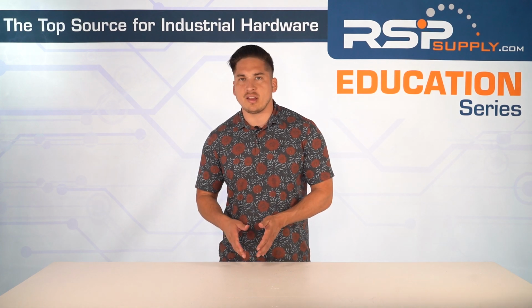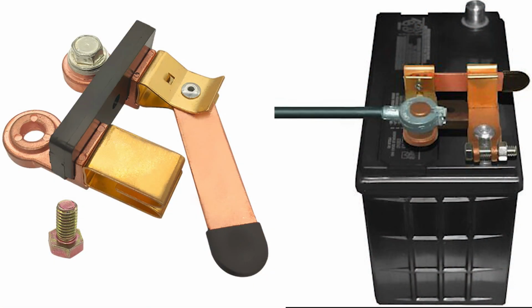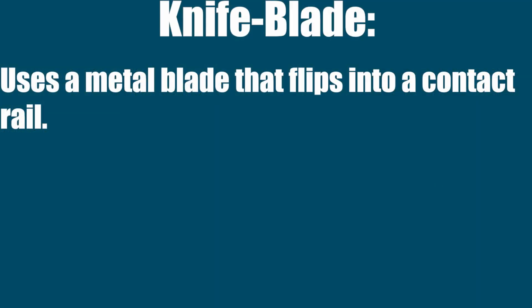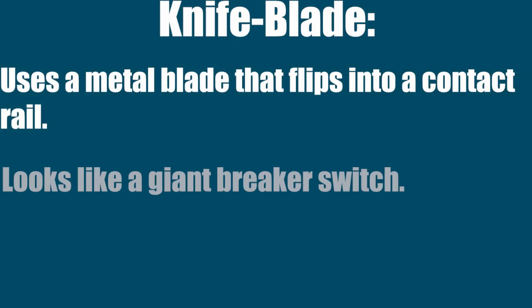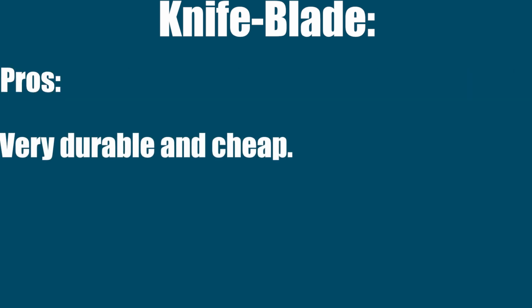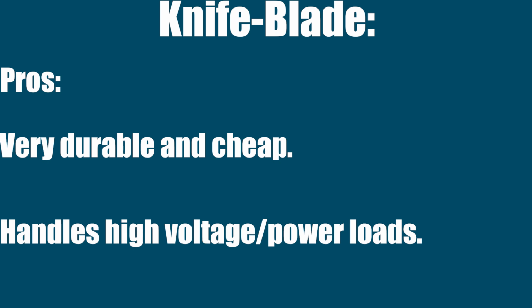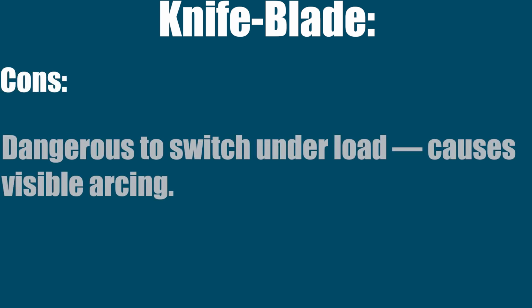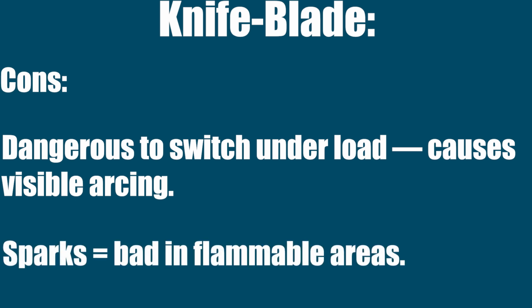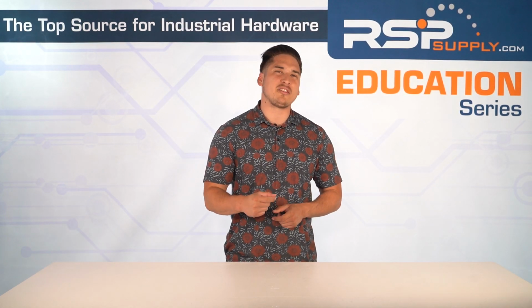Let's talk knife blade versus rotary versus molded case disconnects. So knife blade disconnects, this is old school tech, but still in play. It uses a metal blade that flips into a contact rail. Looks like a giant breaker switch. Pros of this: very durable, very cheap. It handles high voltage in power loads. Some cons: it's dangerous to switch under load since it causes visible arcing. Also causes sparks. That is not good in flammable areas. Best used in large industrial equipment where switching is rare.